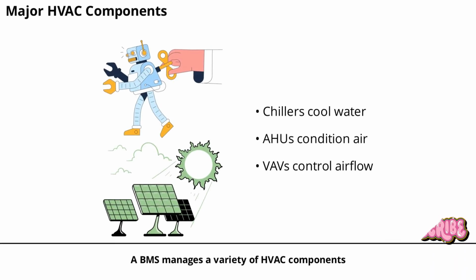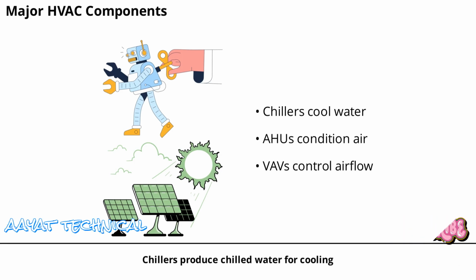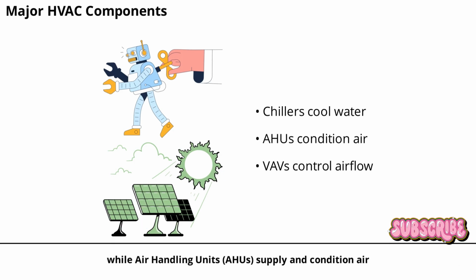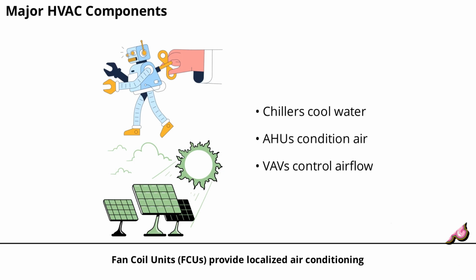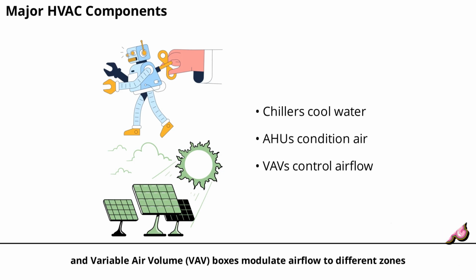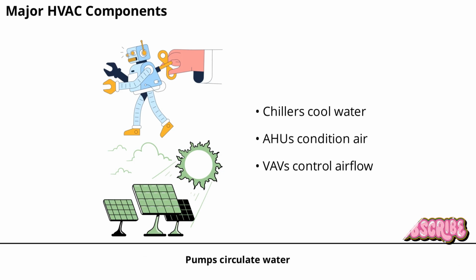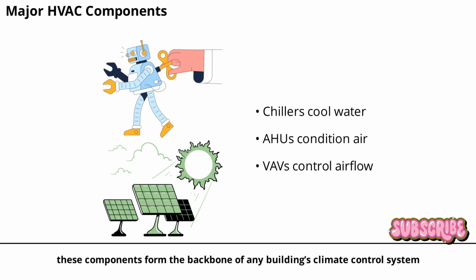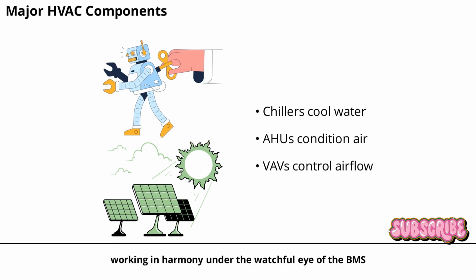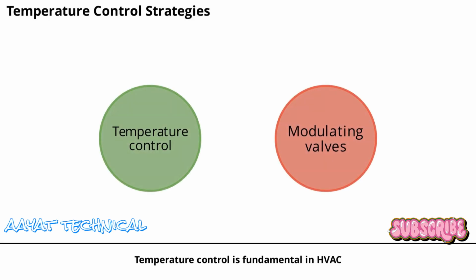A BMS manages a variety of HVAC components, each with a unique role. Chillers produce chilled water for cooling, while air handling units, AHUs, supply and condition air. Fan coil units, FCUs, provide localized air conditioning, and variable air volume, VAV, boxes, modulate airflow to different zones. Pumps circulate water, cooling towers reject heat, boilers provide heating, and dampers and valves regulate airflow and water flow. Together, these components form the backbone of any building's climate control system, working in harmony under the watchful eye of the BMS.